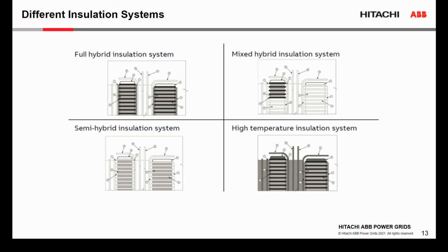And here are some details about different insulation systems. So with full hybrid insulation system, we have high temperature insulation on the winding conductor between the turns and discs, and in the oil ducts, in the vertical oil ducts next to the windings. In mixed hybrid insulation system, we have only high temperature insulation in the area where we see that the temperature is much greater than in other locations. So usually it is on the top of the winding. So the paper conductor in this area is high temperature material, the same as the spacers.